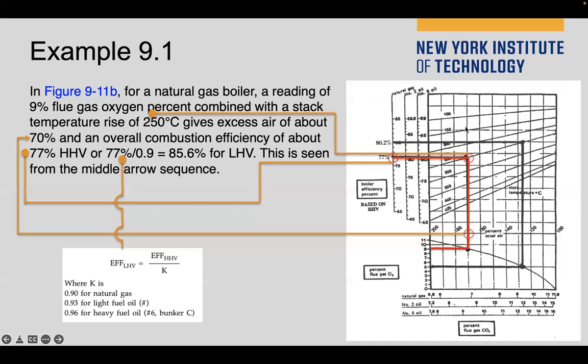So if the stack temperature is lower, this line will go upward, and you can obtain a lower stack temperature with a higher efficiency. So just want to let you know, this is one of the parameters to determine the efficiency of the boiler.